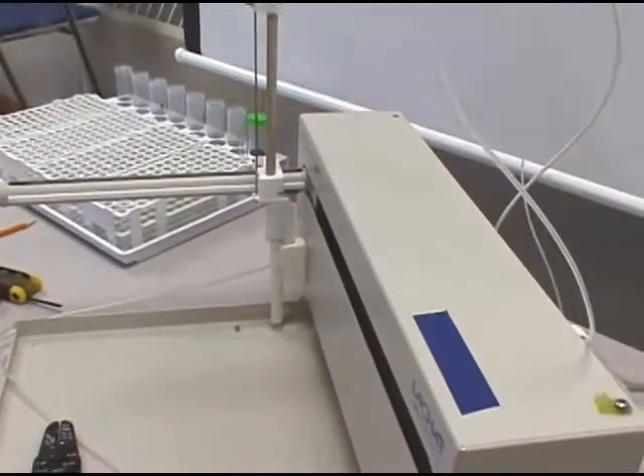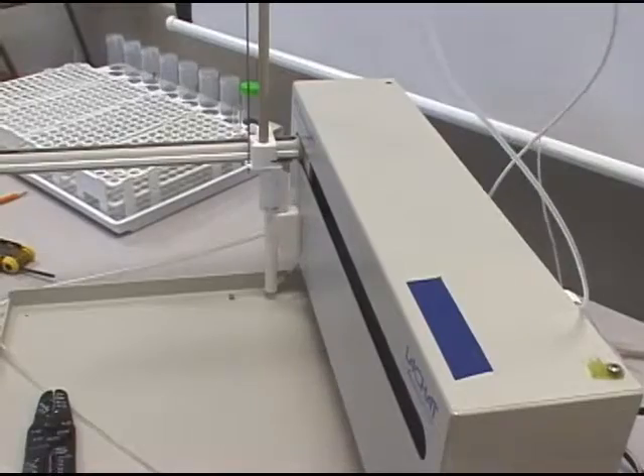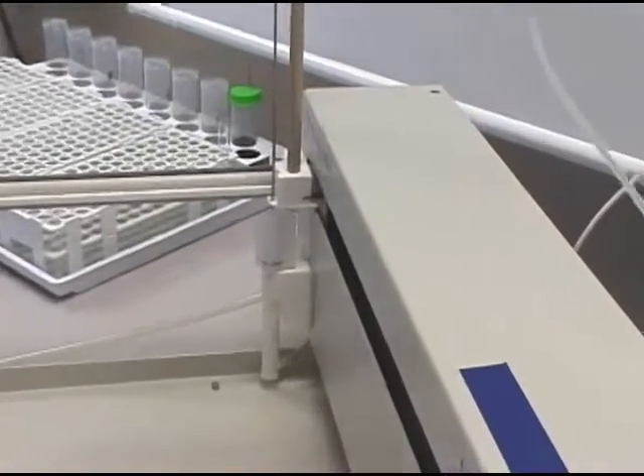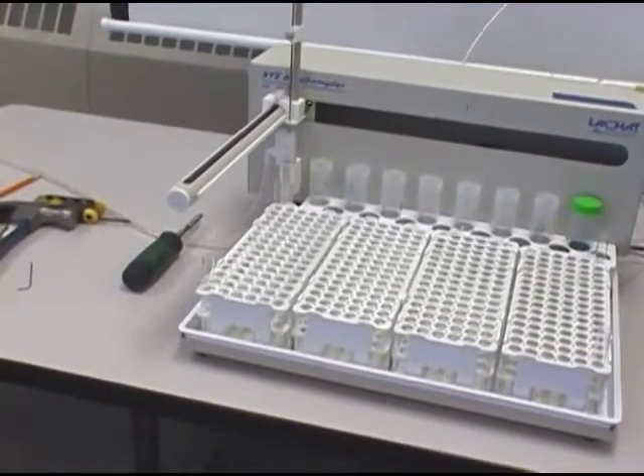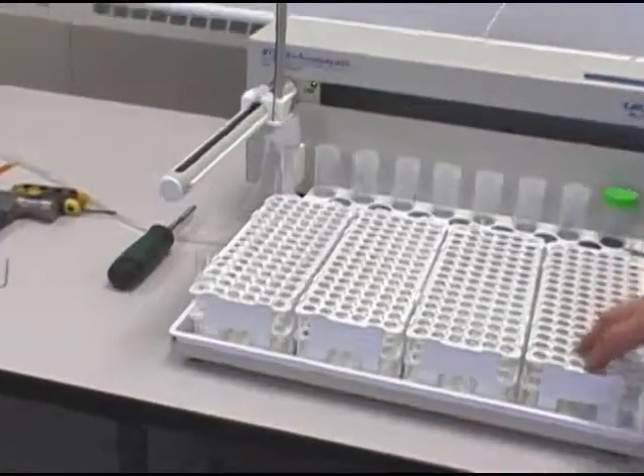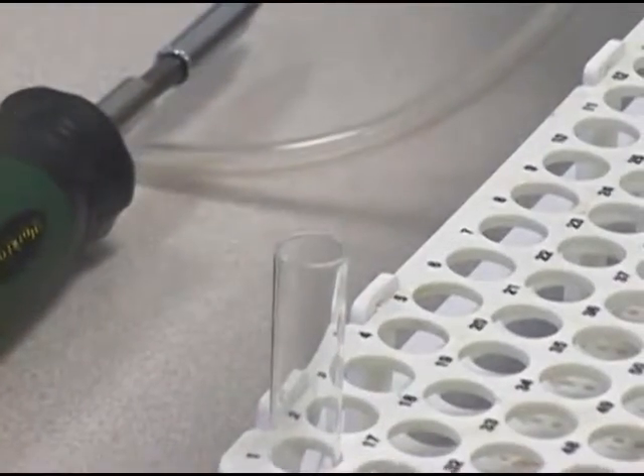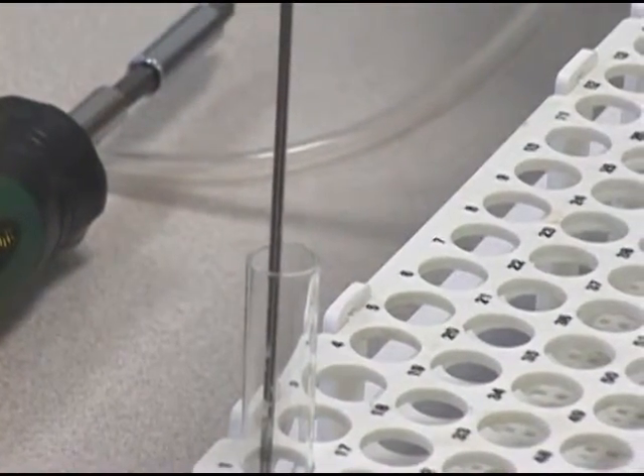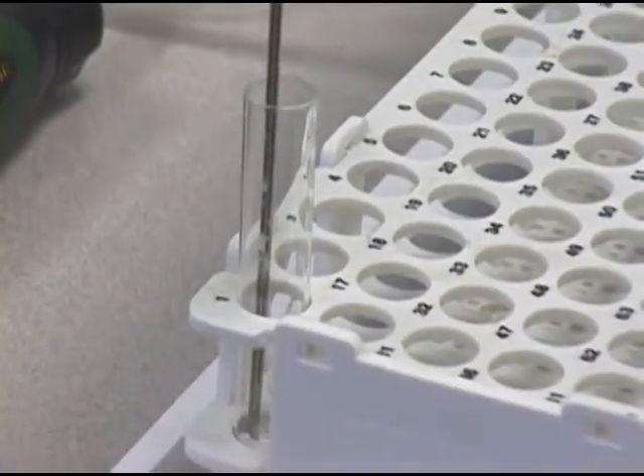We'll then restart the autosampler, let it center itself, and see how close we are to getting the probe back into the middle of the wash cup. And now we've got good clearance all around, and the probe is able to go into the wash cup. Now that we've got the autosampler centered on the wash bath, we may need to center it actually on the sample cups. In this particular case, you see that the alignment is not very good here on the sample cup, and we'll need to make some adjustments.